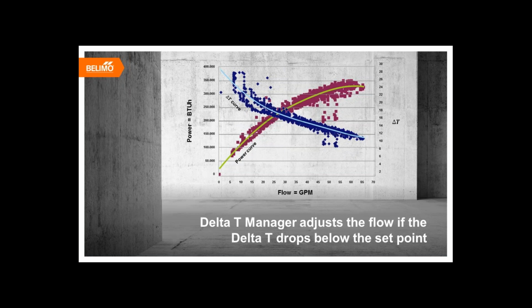If we take a look again at the example we used from MIT, we can eliminate the extra flow in the waste zone by setting a delta T manager to limit the delta T to 12 degrees. By setting this delta T at 12, we're able to reduce the extra flow from 65 to 55 GPM, as the Energy Valve realizes the delta T is dropping below set point and reduces flow through the coil, eliminating the waste zone, or all the additional flow beyond 55 gallons per minute.